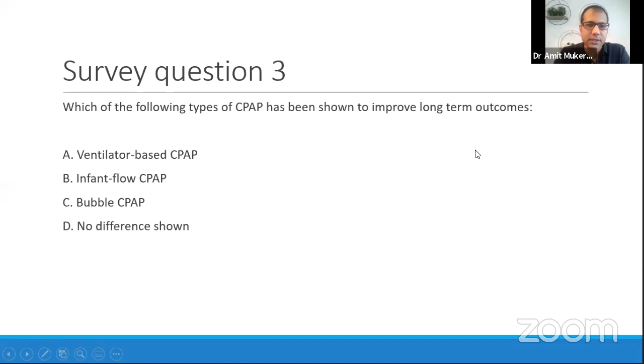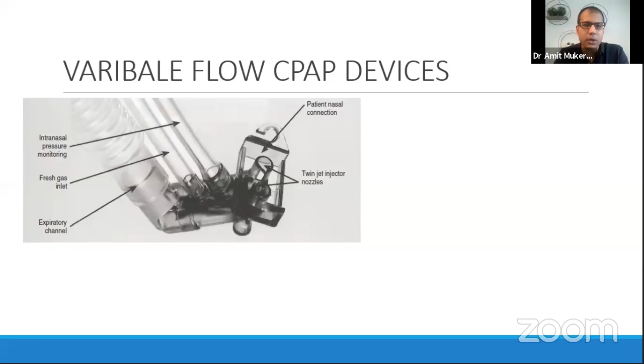I do want to mention briefly variable flow CPAP devices because they're a little bit distinct from how the other CPAP devices work. And again, if you use a variable flow CPAP device in your unit, it would be important to know in detail how the mechanism works. So this is using the infant flow device as an example. And what they have here is the inspiratory gas flow, a column that actually monitors the pressure within the interface, and the expiratory channel.